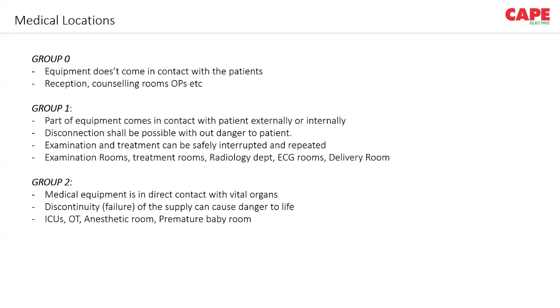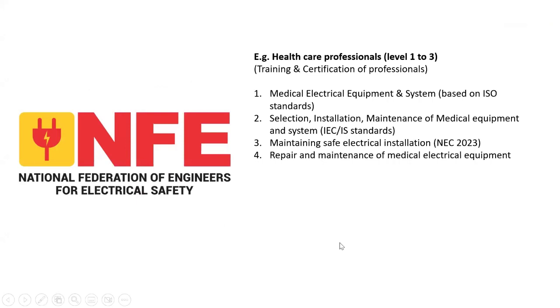For example, if we take care of all the loose wires, all the earth wires, all the insulation failures, even then that is not actually sufficient for a medical location to have a good electrical installation, a complaint-free or a safe electrical installation. It consists of several subjects.